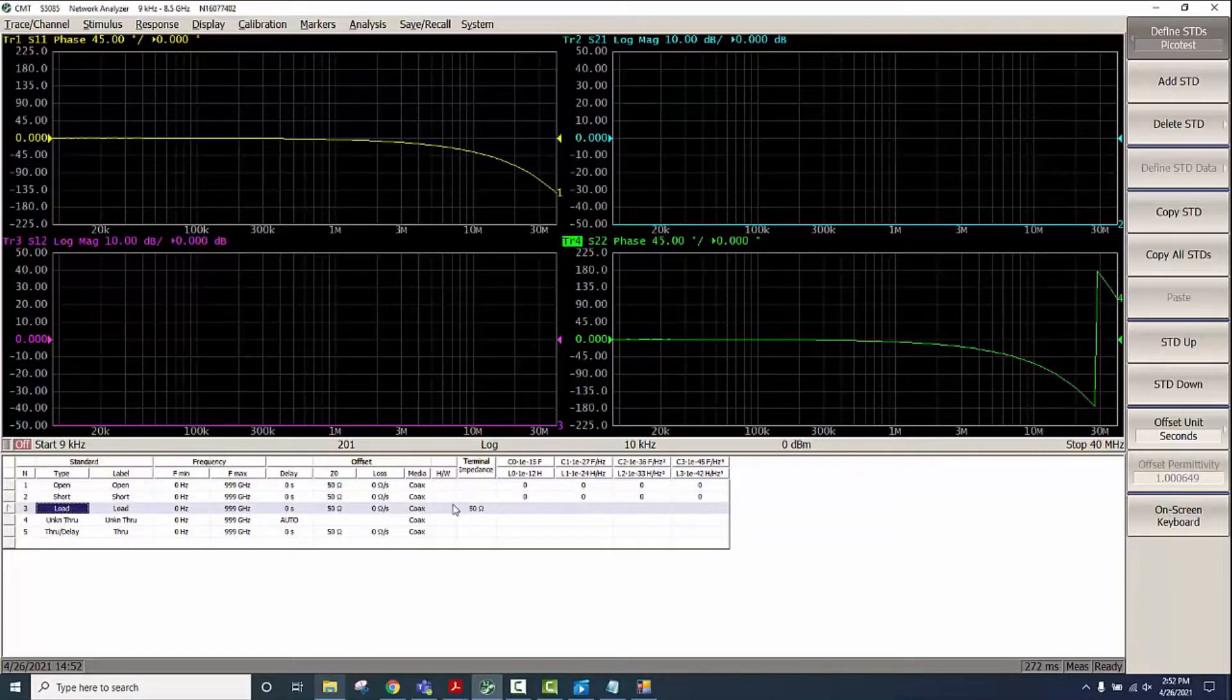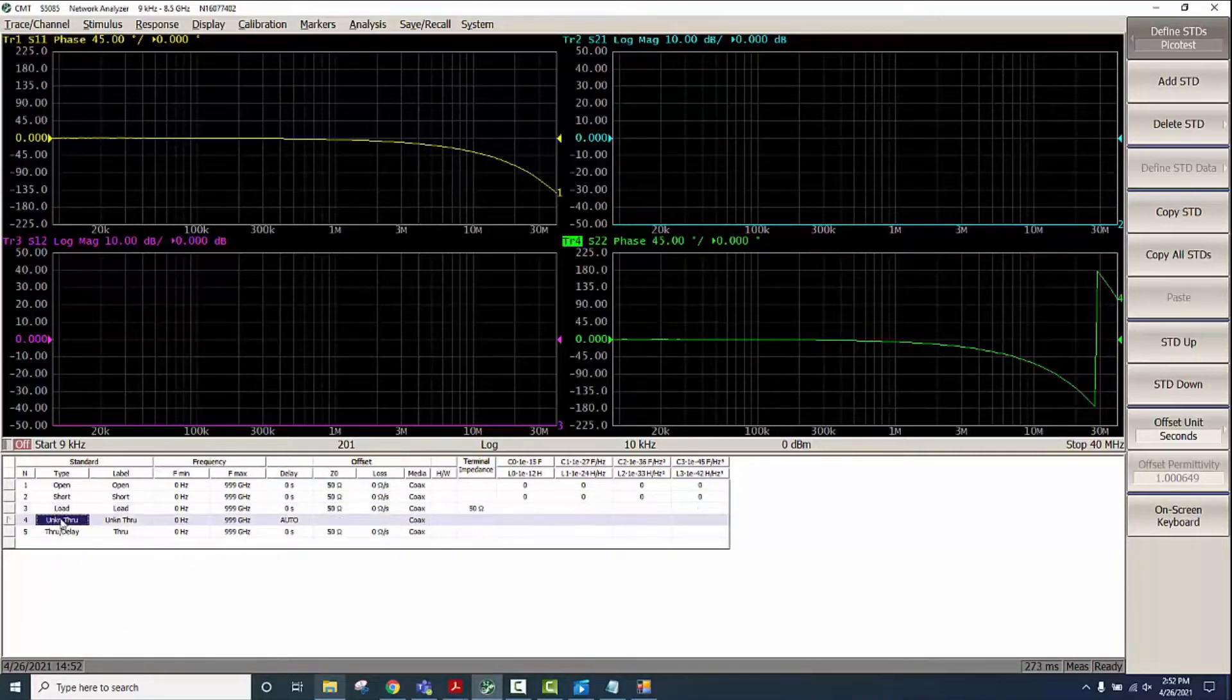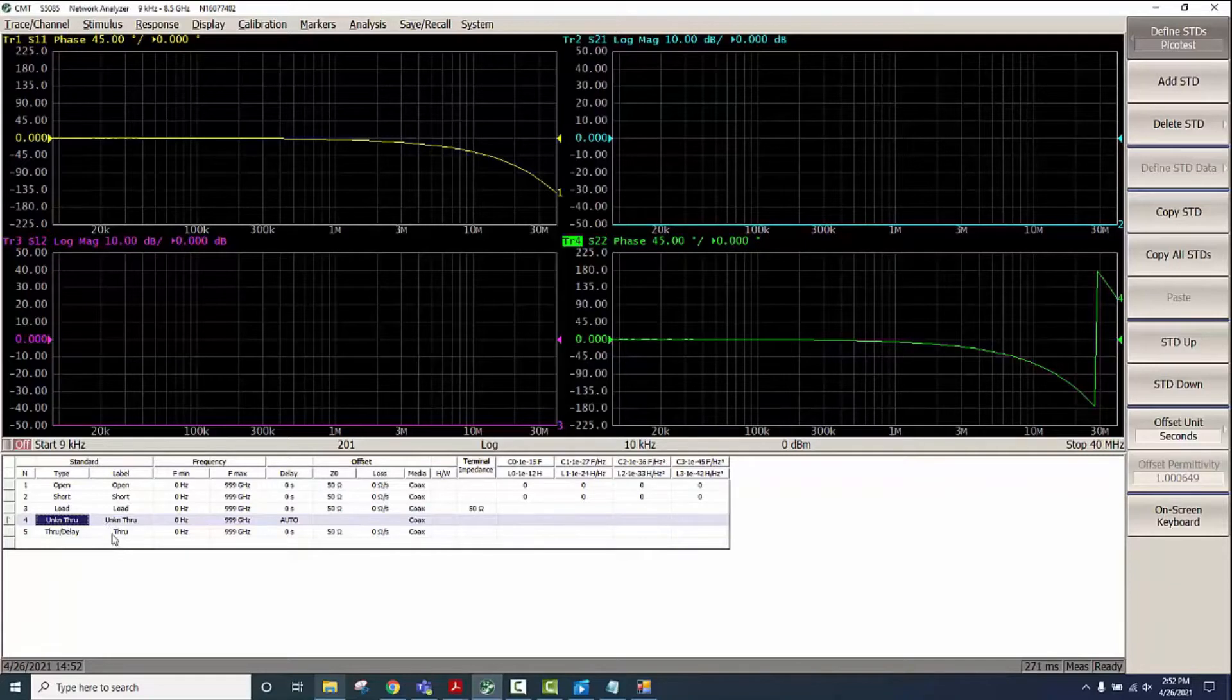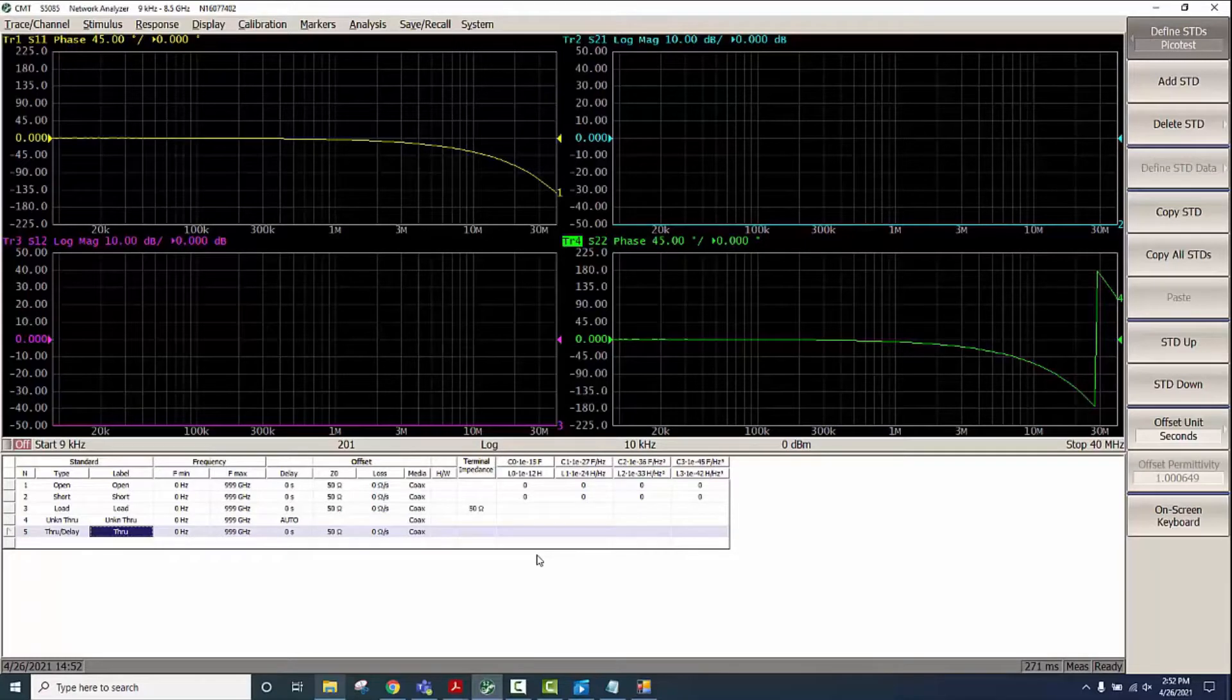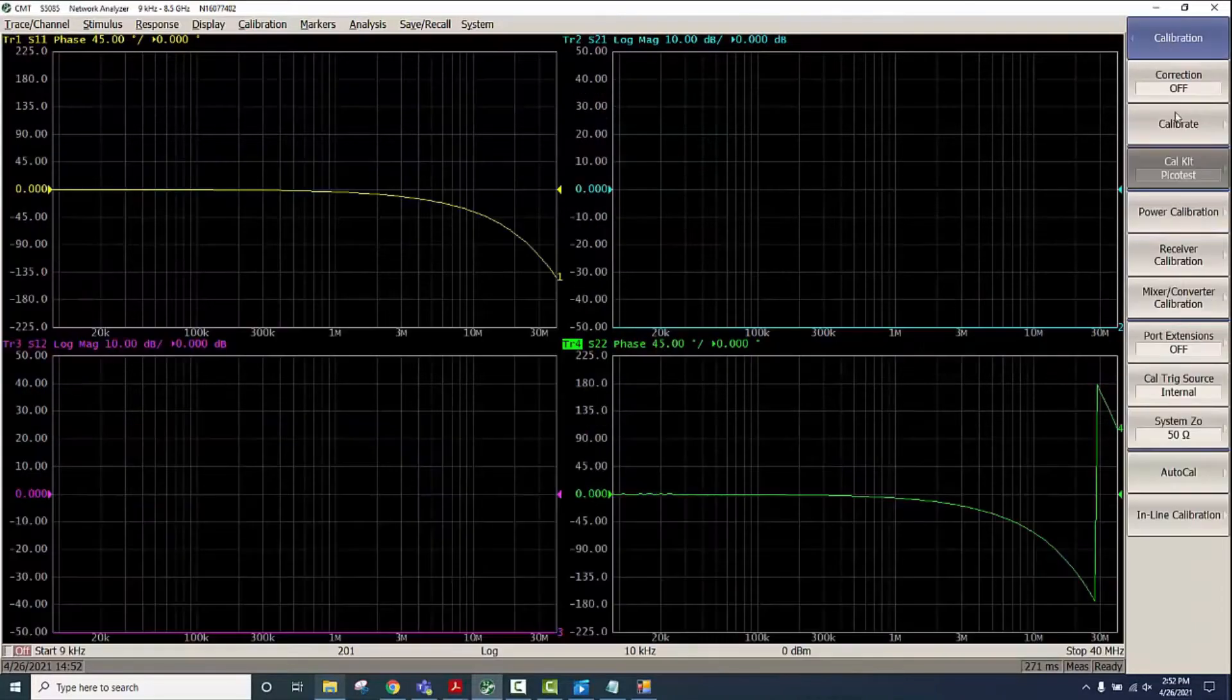For Load we'll assume an ideal 50 ohm load. We'll use Unknown Through, so that's why we are selecting Unknown Through here. We will be performing the full two-port calibration, the SOLR calibration, so we have the Unknown Through defined here. Now that we have it defined properly we'll go to Calibrate.